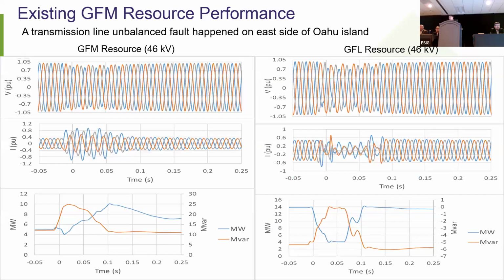Yeah. This is the 46 kV GFM resource, and the 46 kV GFL resource. So the GFM one, the response is similar to the 138 kV GFM resource response. So again, we see strong support to system stability and also strong support to the recovery from the fault.